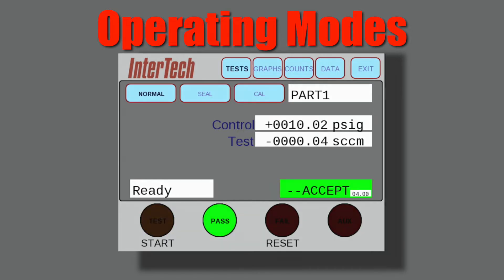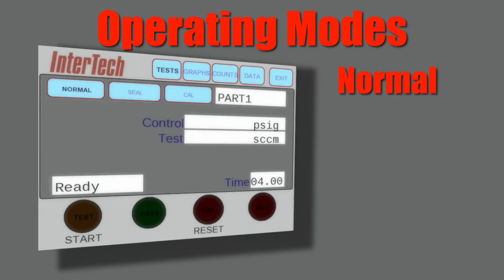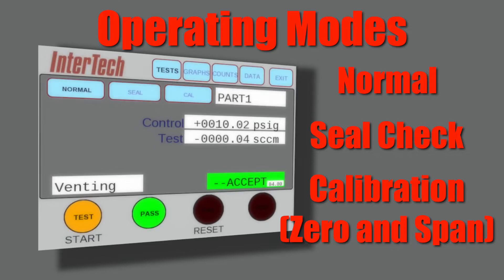The user can select normal mode for standard test cycle operation, seal check mode which allows the test circuit and seal troubleshooting, or calibration mode which allows for full calibration of the unit for both zero and span calibrations.